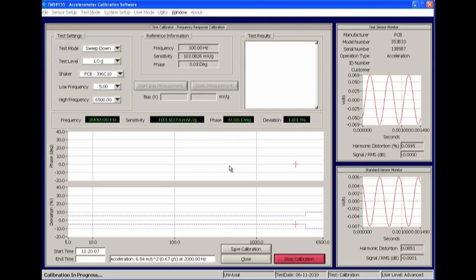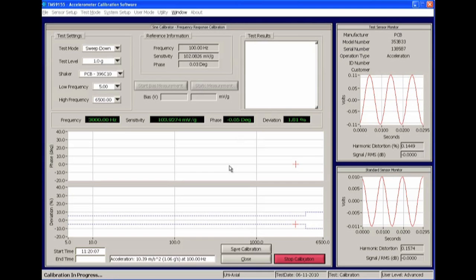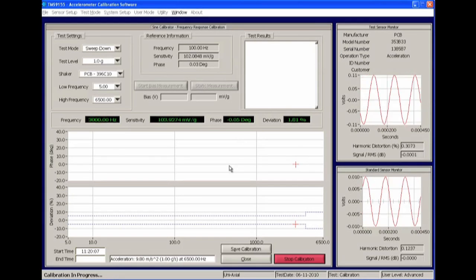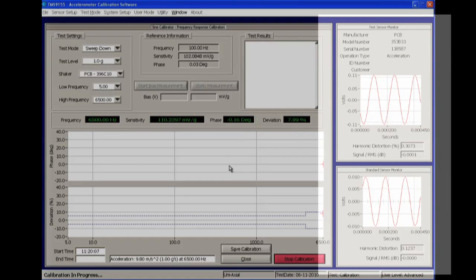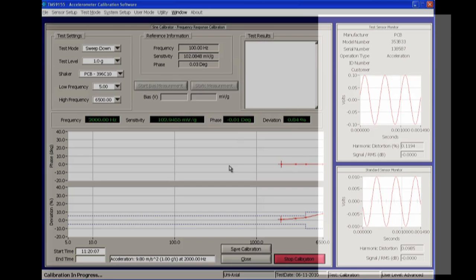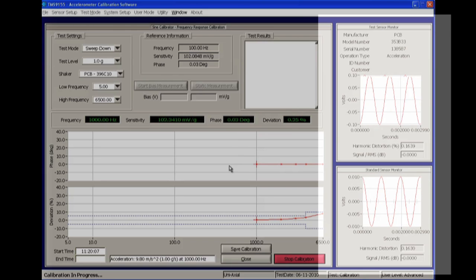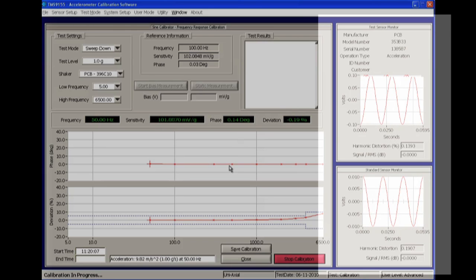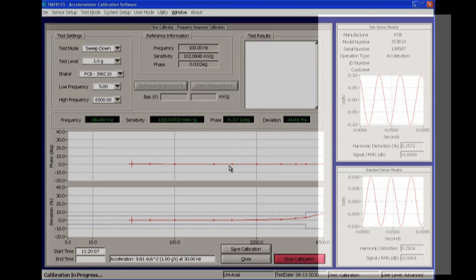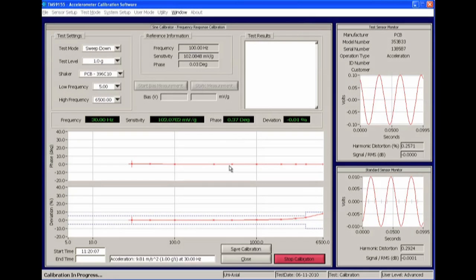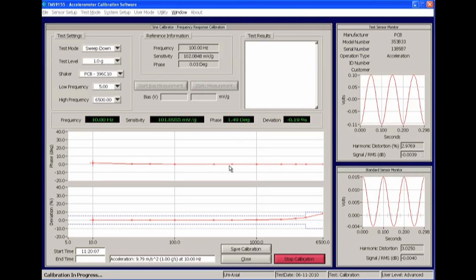As the test runs, the software will display the voltage output signals of both the reference and sensor under test. These displays can be useful for detecting and troubleshooting sensor issues such as intermittent connections or no output conditions.